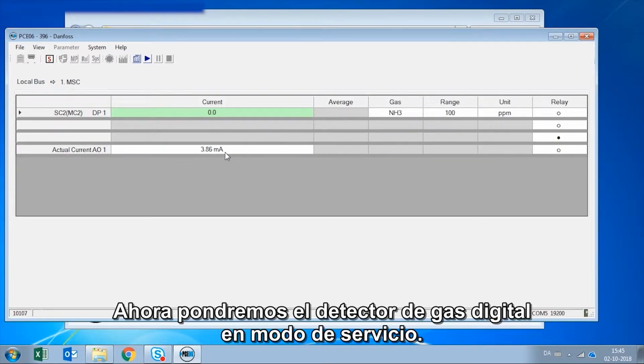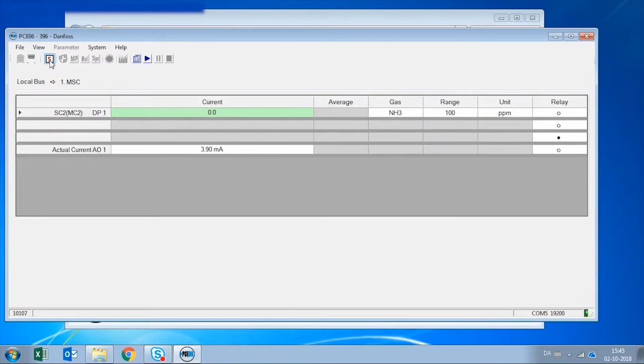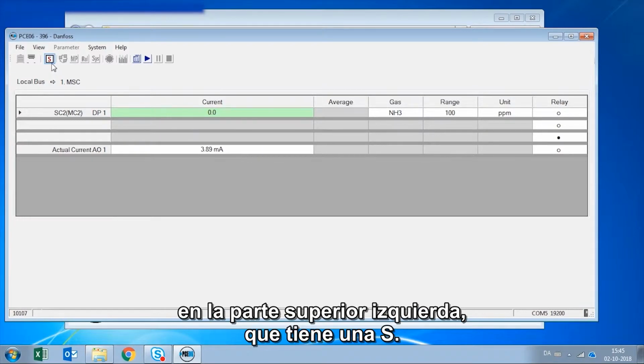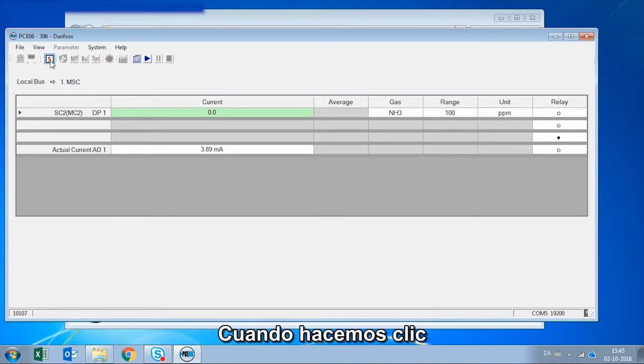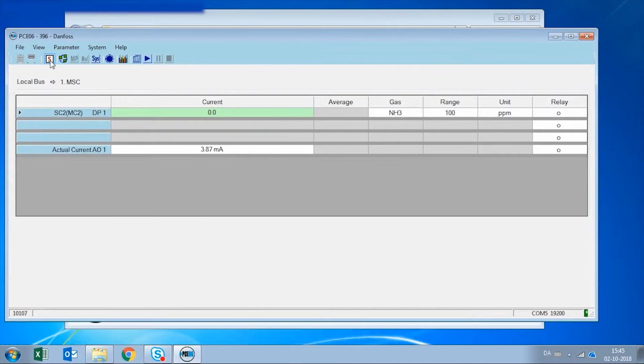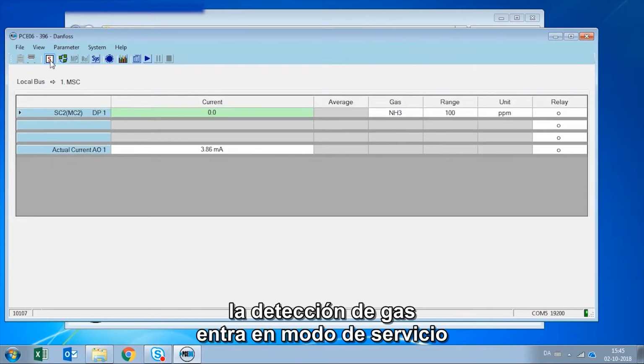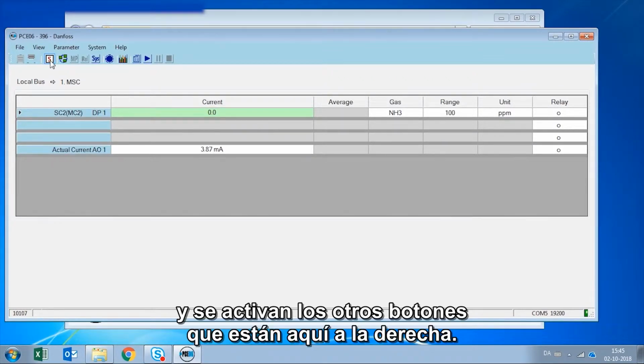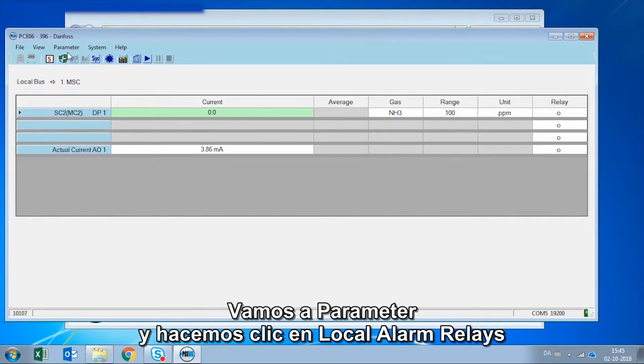Now we are going to put the digital gas detector into service mode, and for that we are going to click this button on the top left, that is an S. The moment we click it, the gas detection goes into service mode and we are allowed to see the other buttons that are here on the right. We're going to go to parameter and click local alarm relays in order to activate all different options.